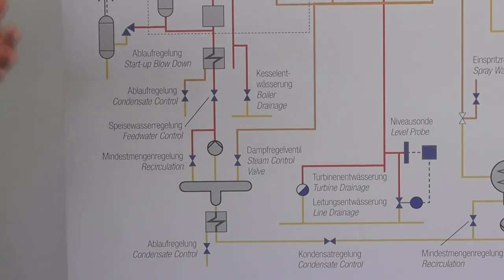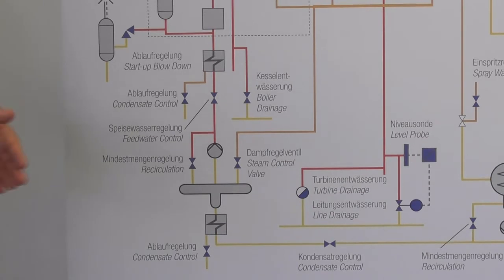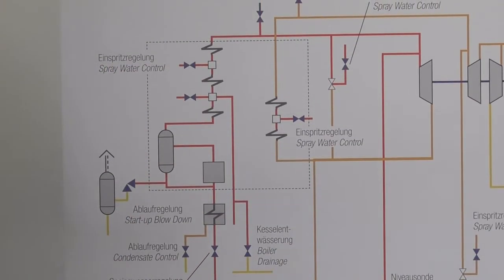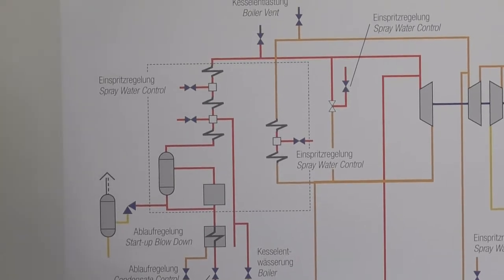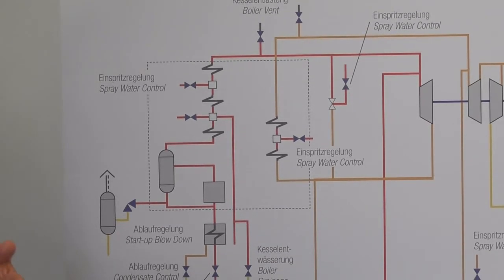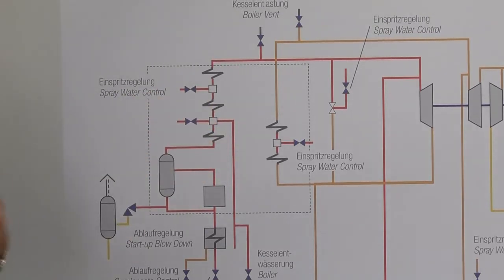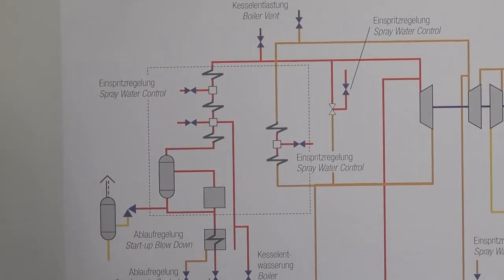Another application where a perfect tight shutoff is very important are the spray water control valves. If these valves are leaking, then thermoshock crack damages may appear at the steam coolers or at the bypass stations for the turbine.